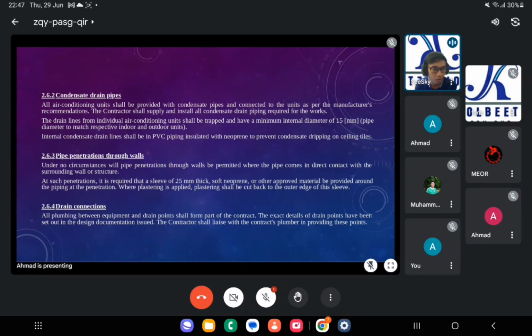2.6.2 Condensate drain pipe. All air conditioning units shall be provided with condensate pipe and connected to the unit as per manufacturer recommendation. The contractor shall supply and install all condensate drain pipe required for the work. The drain line for individual air conditioning shall be trapped and have a minimum internal diameter of 15 mm, pipe diameter to match respective indoor and outdoor unit. Internal condensate drain line shall be PVC piping insulated with neoprene to prevent condensate dripping on ceiling tiles.